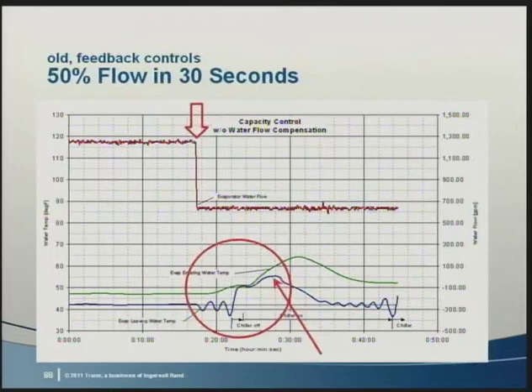When we reduce the flow, the chiller becomes unstable, hunting for the set point with the change in flow. With the instability, the chiller reaches its differential to stop and the chiller cycles off. As the chiller is restarting, the temperature of the chilled water loop continues to increase, and when the chiller does come back on, it has to pull the temperature gradually back down to set point. So why is the chiller unstable? Because the design delta T is set at full flow. For example, a 10-degree delta T at full flow would be 20-degree delta T at half flow. And if the adjustment for the inlet guide vanes is set to full flow, the adjustment would be too coarse for the part flow.